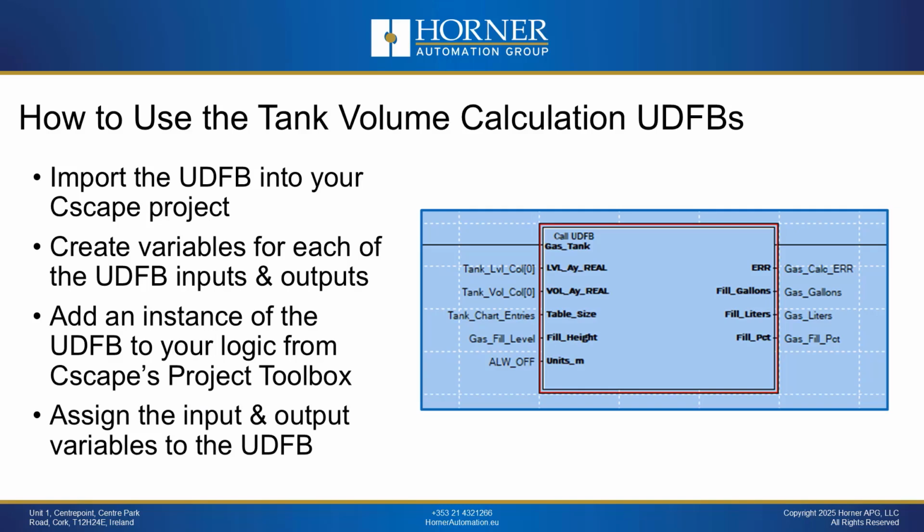You are going to import a UDFB into your Cscape project, and create variables in your program's variable window for each of the UDFB inputs and outputs. Next, you're going to add an instance of the UDFB into your logic program. You'll find those UDFBs that have been imported in your project toolbox.